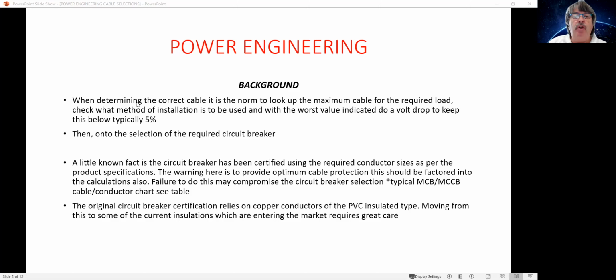But there is a little known fact that the circuit breaker has been certified with a certain conductor size as per the product specifications and manufacturing thereof. The warning here is to provide an optimal cable protection that should be factored into the calculations also. Now, this is not generally known by the trade. Of course, it's more of a manufacturing type of thing. And you could, in fact, choose a different, both a miniature circuit breaker or molded case, and the cable size could be slightly out of sync, and it could have a negative effect onto the performance of a circuit breaker.